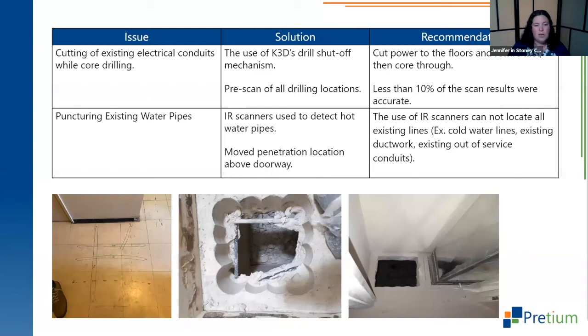So in locations where our as-built construction drawings weren't particularly reliable and the scanning wasn't picking up everything we were finding, we identified those riser locations and made the adjustment to shift the penetrations over the doorway. That helped ensure there wouldn't be any existing services in that space. It meant reconfiguring some bulkheads and ductwork inside the units, but we were able to do that in a way that was still visually appealing.